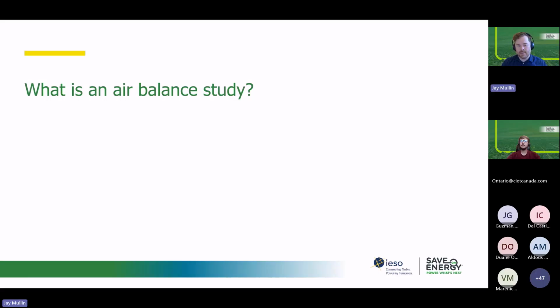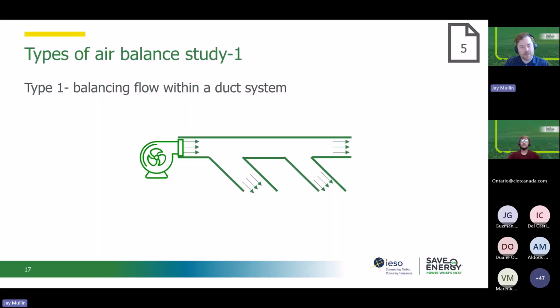So what is an air balance study? So at the beginning, we talked that there's two types. We're going to call them type 1 and type 2. These are not official names, but just so we can distinguish them. The first type is that duct terminal flow balancing. So that focuses on balancing airflow within a duct system so that each diffuser grill terminal receives the designed airflow and pressure. It can solve issues with uneven temperatures between zones, some diffusers delivering too much air, some not enough, and verifying that the system performs as designed, particularly after installation or modification.